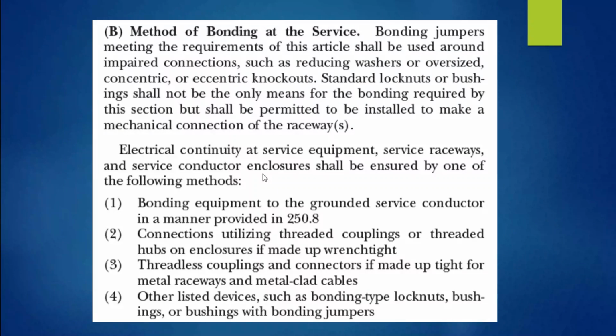So B is going to say, okay, of those allowed things that you have to bond together in 250.92(A), here are the methods. So bonding jumpers, meeting the requirements of this article, shall be used around impaired connections. We talked about that, such as reducing washers or oversized concentric or eccentric knockouts. Standard locknuts or bushings, just a standard bushing, shall not be the only means of bonding required by this section. Okay, we're doing a little bit more enhanced type of bonding here, but shall be permitted to be installed to make the mechanical connection.